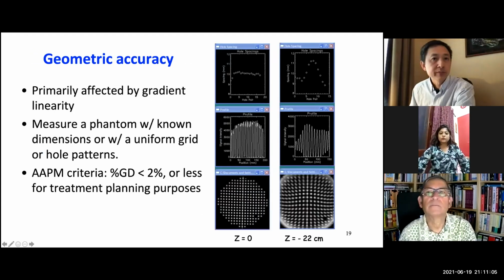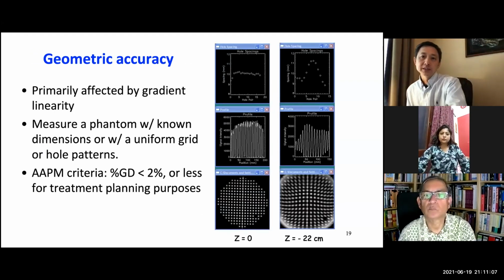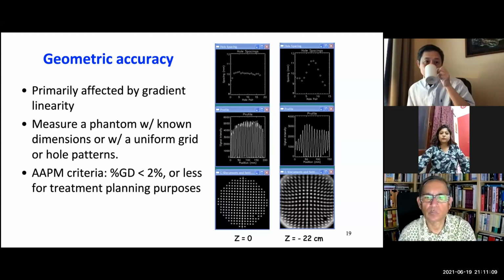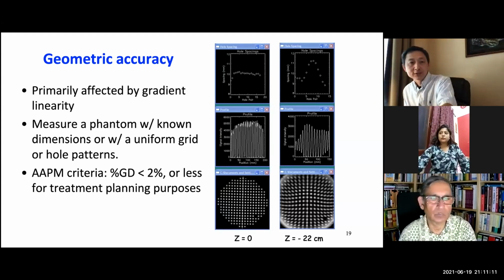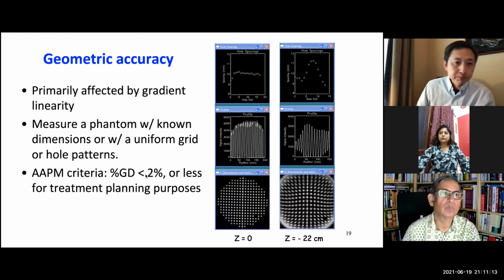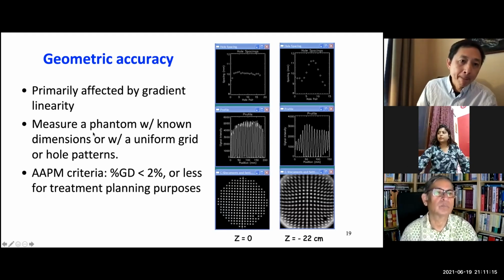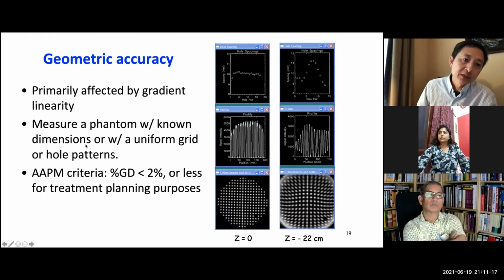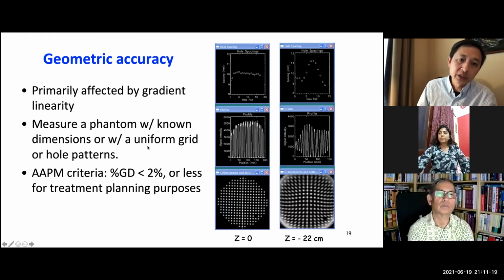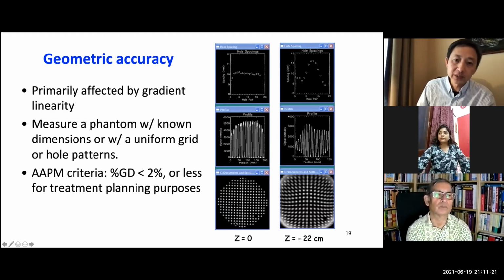So about the geometric accuracy, basically, it's affected by the gradient linearity. And we can use a phantom with known diameter like the ACR phantom, or we can use a uniform grid or hole phantom like the phantom result shown here.